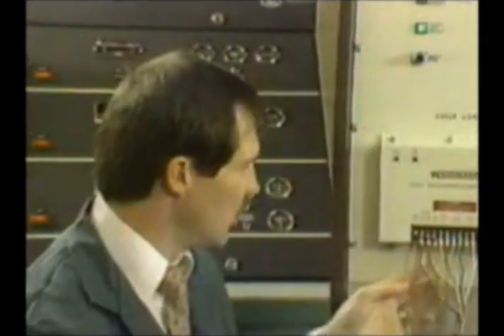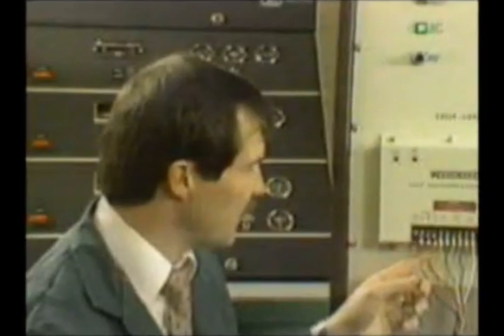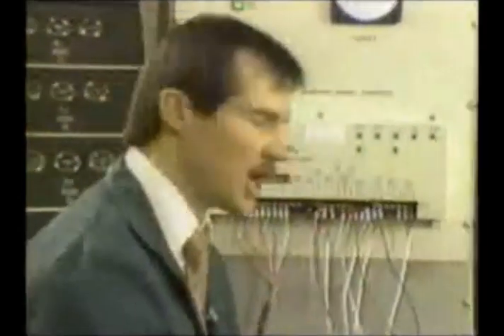Now this brings us to a point of phasing corrections for your PTs and CTs. Now with the engine running, we have 120 volts AC from A phase to B phase, B phase to C phase, A phase to C phase. But you could still have one of your CTs turned around, reversed, or you could have them hooked up incorrectly. Now, a very simple test for that is when you're at this point, you've set up your load gain voltage. You need to stop the engine. So let me go ahead and stop the engine.